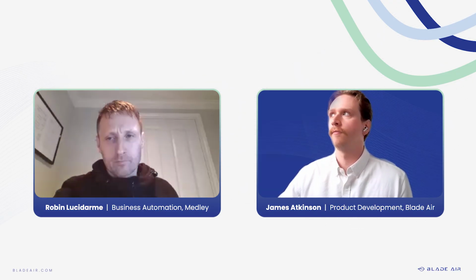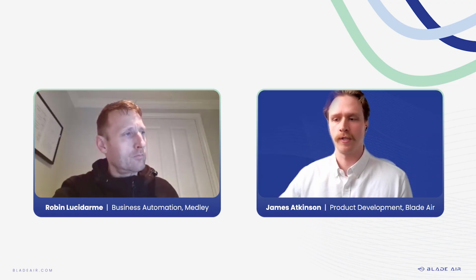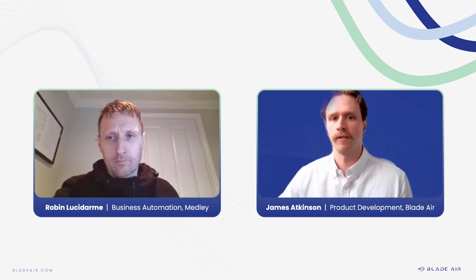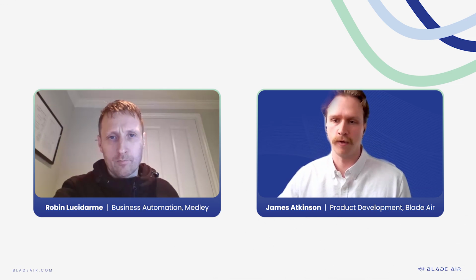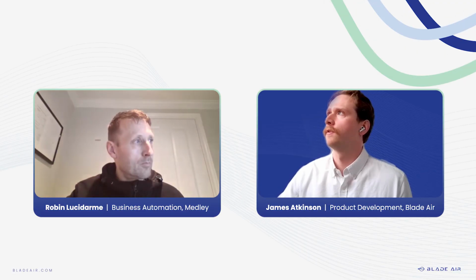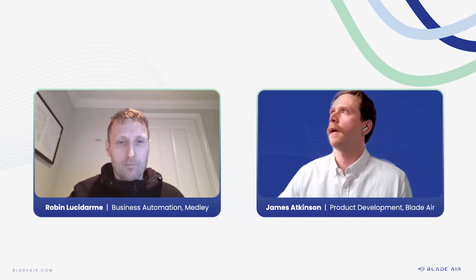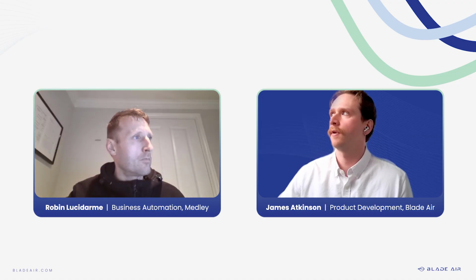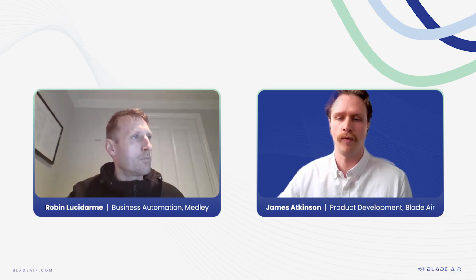So if you do have more than, let's say, 12 filters, we will usually just send you a transformer to go along with them so that you're not pulling too much load off of the control panel. Smaller filters, let's say 6 or lower, we just go right off the control line because that's 24 volts AC. Can it replace the MERV 13 bag filter in kitchen exhaust filter units? We have done that. I think there was a fast food restaurant that used our filters with quite good results. I am not as familiar with the standards for kitchen. I'm not sure if there's a specific requirement for, say, the grease because it's from a kitchen environment, but we have done it.